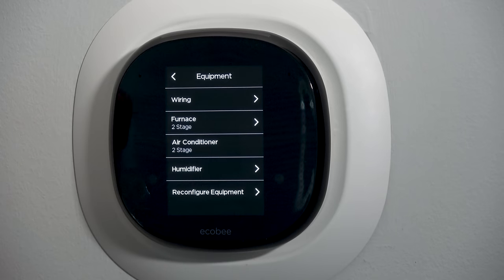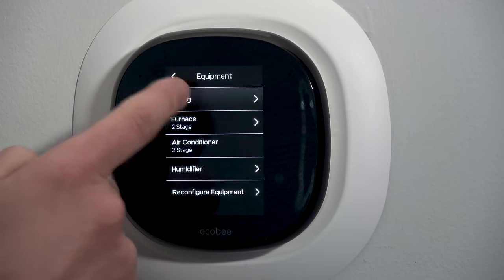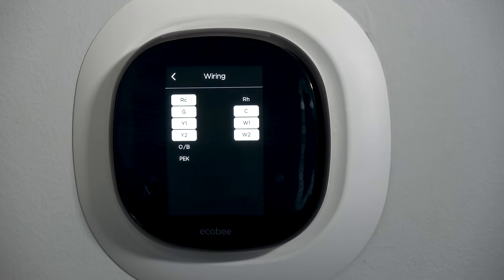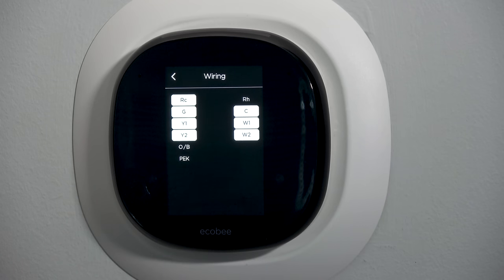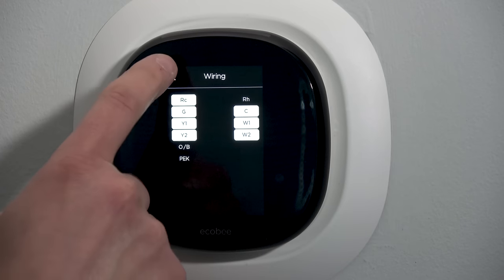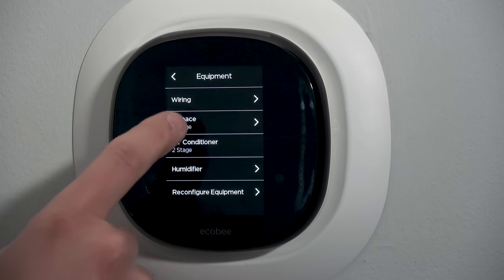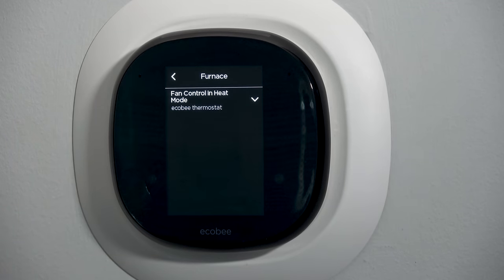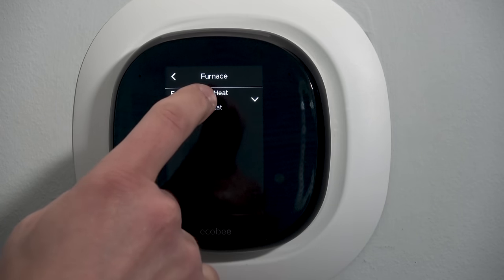The first section, equipment wiring scenario, tells me the terminals I'm actually using on this thermostat. You can't change it from here — if you need to change it you need to go back, reset the thermostat, and do a reinstall. But it tells me what I actually have, so I know if the person who wired this wired it to what I actually have for my equipment. In this case: furnace, two-stage.